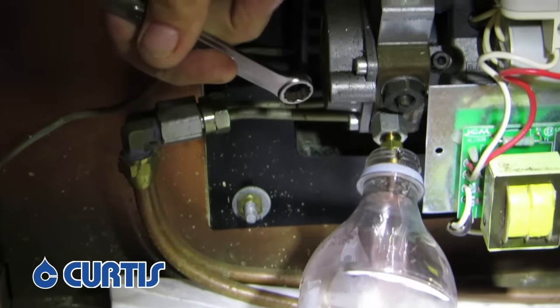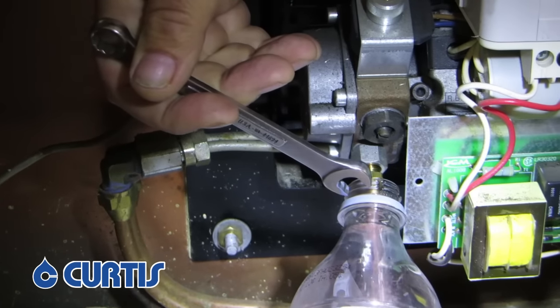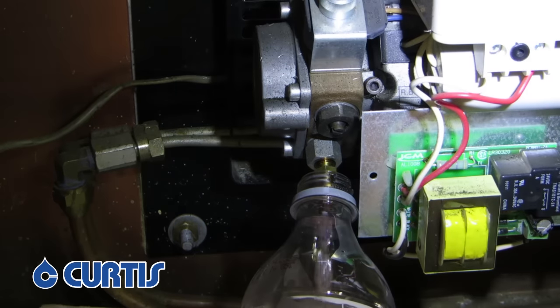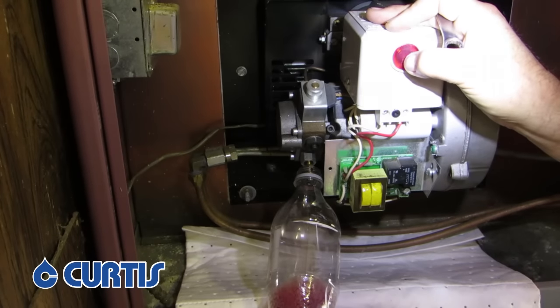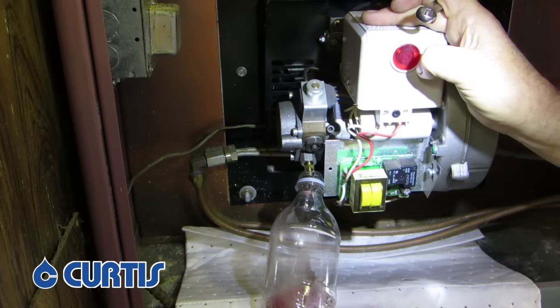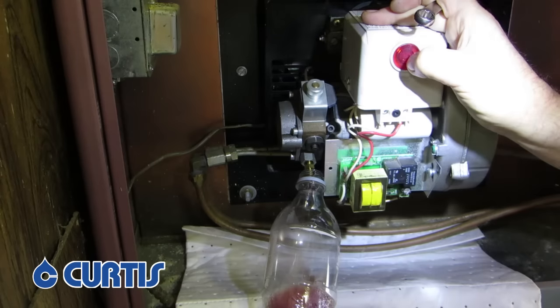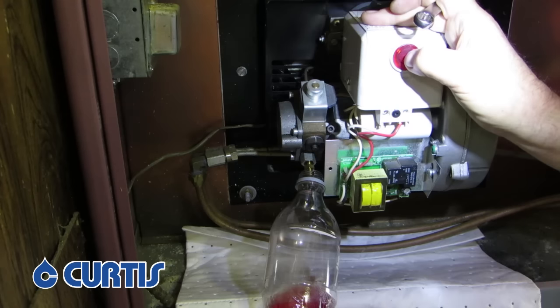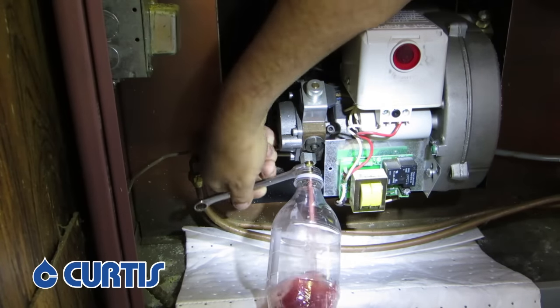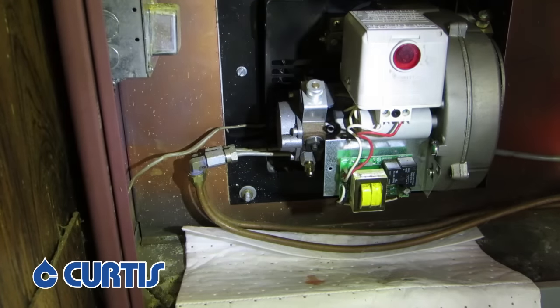And here we go — it's going to be coming out again. You can see as we do this, it's starting to become more clear. We'll give it just another minute or so. It doesn't have to be totally clear, but you definitely want to give it a couple of minutes. If it takes you three or four rounds, don't worry about it — just hang out and wait for it to happen again. When it's ready, put your wrench on, wait a little bit for the oil to start, and then just close it. You can hear that the oil went in and the furnace started.